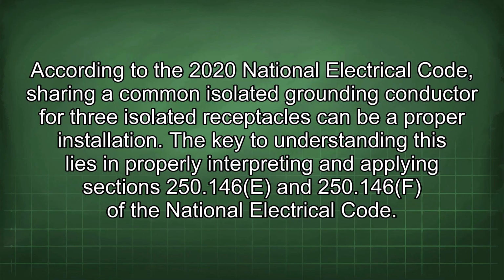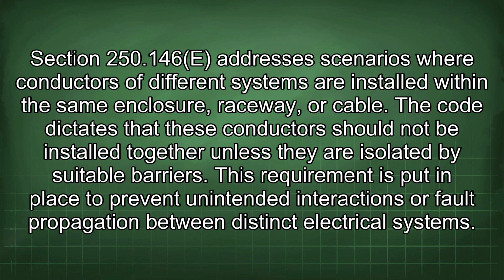According to the 2020 National Electrical Code, sharing a common isolated grounding conductor for 3 isolated receptacles can be a proper installation. The key to understanding this lies in properly interpreting and applying sections 250.146(e) and 250.146(f) of the National Electrical Code. Section 250.146(e) addresses scenarios where conductors of different systems are installed within the same enclosure, raceway, or cable.